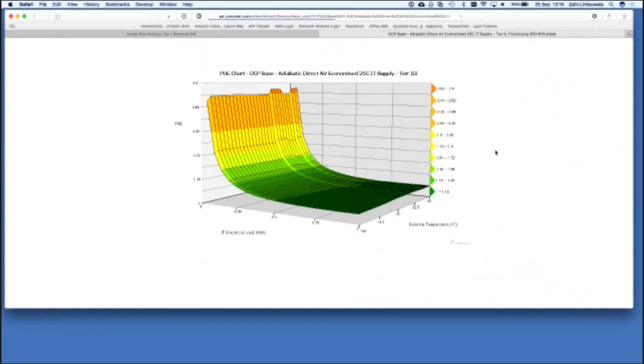This is what I can expect my annual average PUE in Helsinki to be for an OCP adiabatic versus the other options there. So there's a chilled water, there's an economized chilled water, there's an indirect, and then there's an adiabatic, the non-OCP one as well. So I can go in here and select a lower load point, one of the four load points in there, and that will update the results. Or, as I mentioned, I can look at the PUE surface.